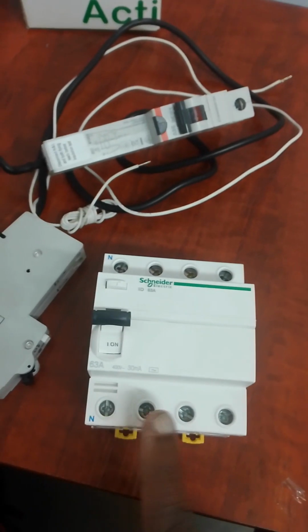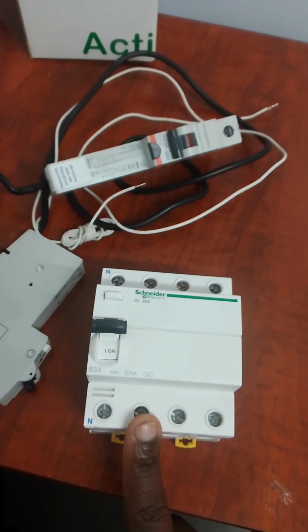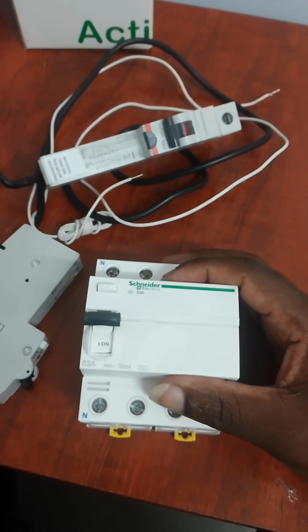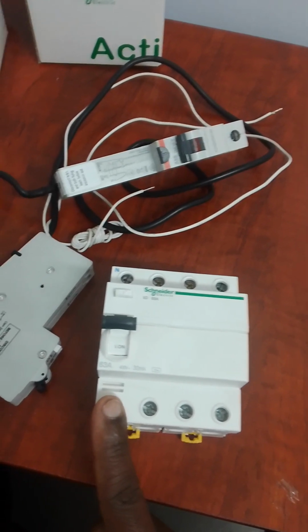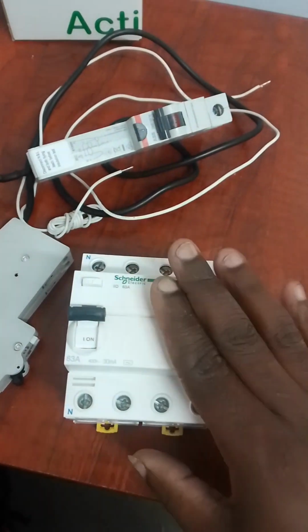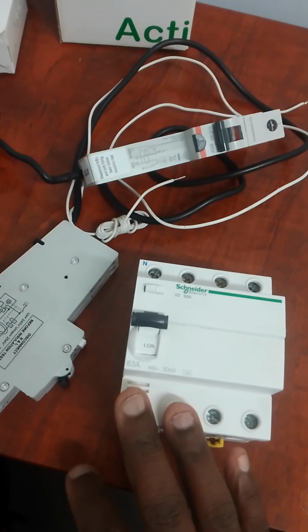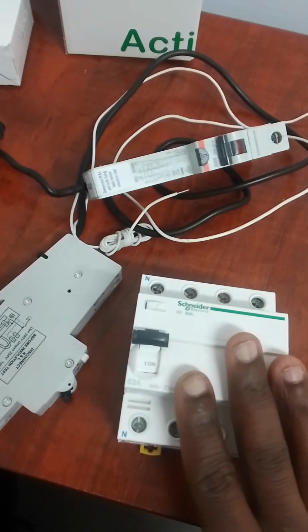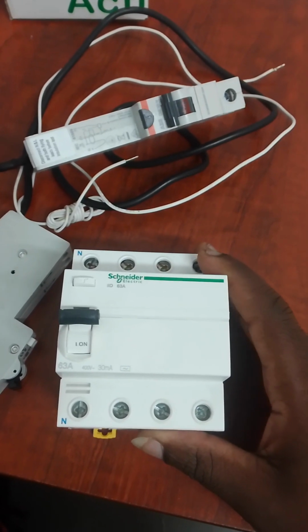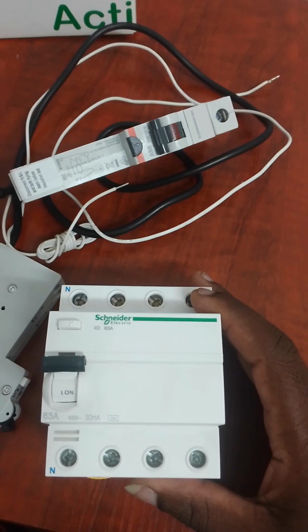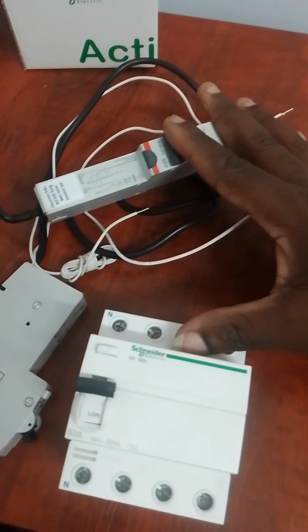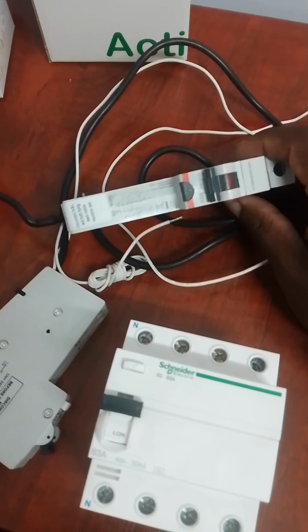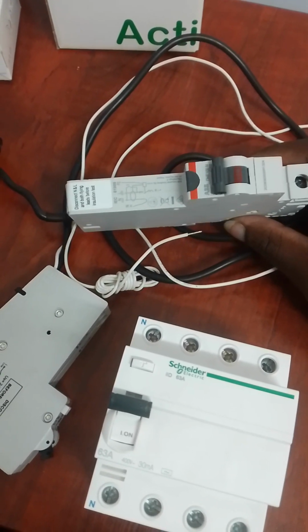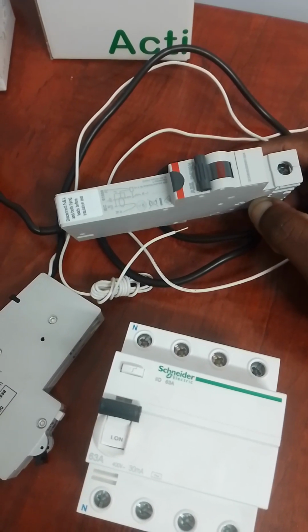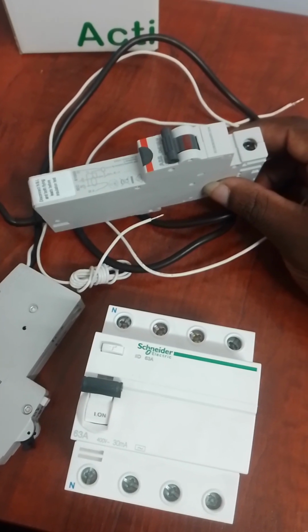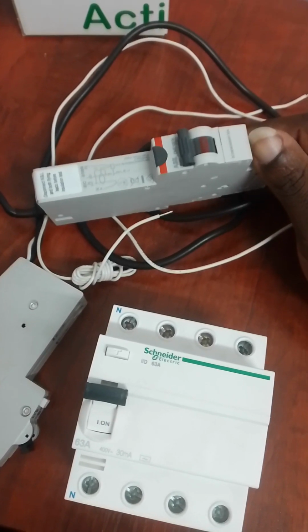This one you connect neutral and three phase. This will protect your circuit. If you get a neutral from a different feeder, automatically this will sense and go off. If there's any problem with the neutral side, it will trip, because it's also a residual current circuit breaker. So this and this have almost the same function, but this one is more advanced because it also deals with overcurrent. So when the end user has a lot of consumption, it will sense it and go off.